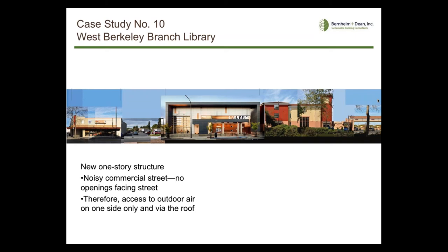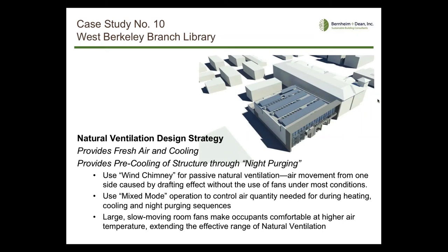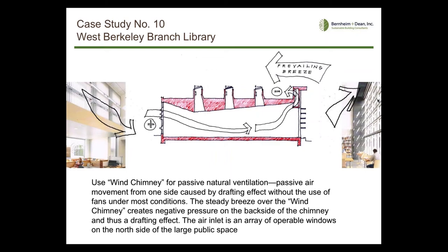The lessons learned were the same. This client did not engage a controls integration consultant from the start. An integrated control system is not currently available in the US, so someone had to program and work with it during construction documents and construction. It took about six months to get the system to work correctly, using a proprietary integration system. The natural ventilation system is a kit of parts requiring a skilled programmer who stays with it to make sure it works — that's a drawback to what we have at the moment. The mechanical operators, again, could only move to fixed positions rather than operating continuously.